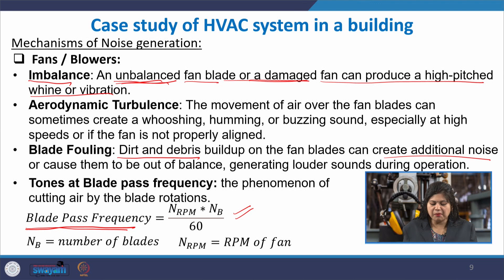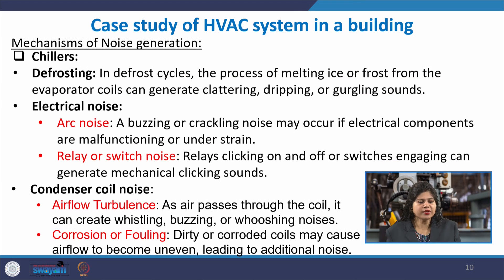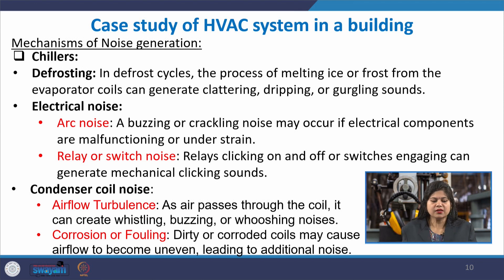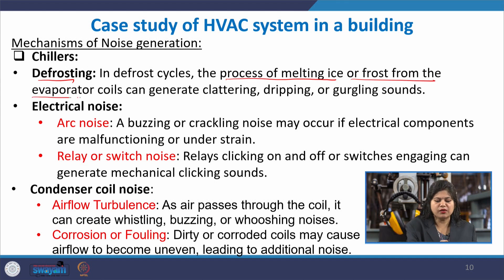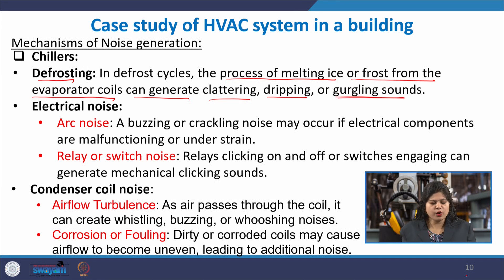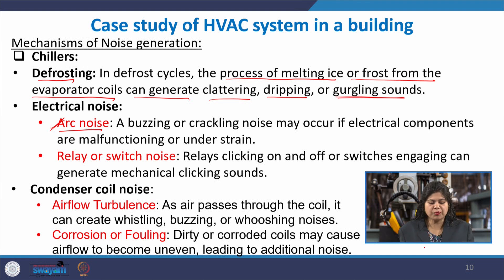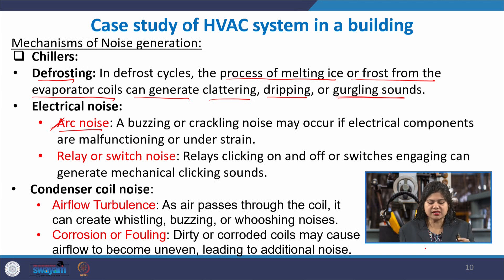For noise generation mechanisms in chillers: the chiller unit is responsible for cooling, and during defrost cycles, the process of melting ice or frost from the evaporator coils generates clattering, dripping, or gurgling sounds. There is also electrical arc noise — a buzzing or crackling noise that may occur if electrical components are malfunctioning or under strain. Relay and switch noise involves clicking sounds from switches engaging and disengaging.